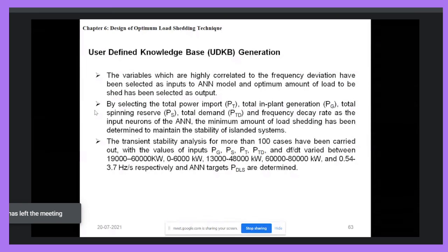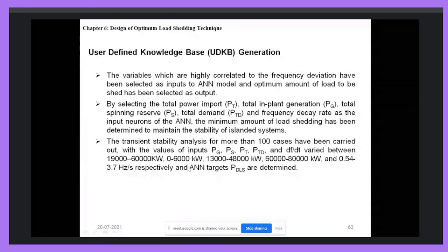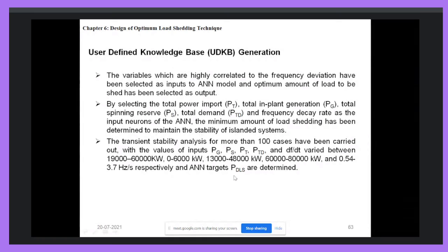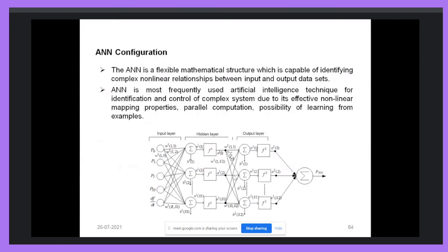These are the variations. You can see here, a 19 to 60 megawatt variation in power generation was considered. In the range of spinning reserve, 0 to 6,000 kilowatt variation was considered. The total demand considered is 13 to 48 megawatt. And for frequency, a variation of 0.45 to 3.7 hertz per second was considered. These are the ranges of inputs considered for the training and testing of the ANN.